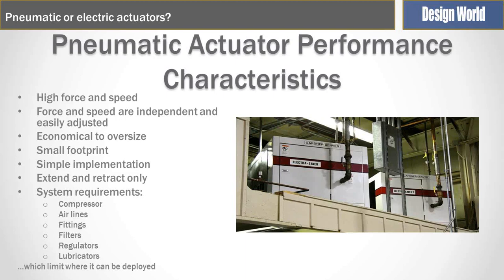A lot of times people go a larger size rather than reducing air pressure to achieve the force they need. Pneumatics have a very small footprint and are relatively easy to implement. A disadvantage is that they are usually extend and retract only. Although closed-loop pneumatic cylinders with position feedback exist, in general they are extend and retract only. There is also a rather involved pneumatic system around the actuators — you require a compressor, airlines, filters, regulators, and lubricators — all of which must be in the vicinity of the installation, limiting where pneumatic actuators can be deployed.